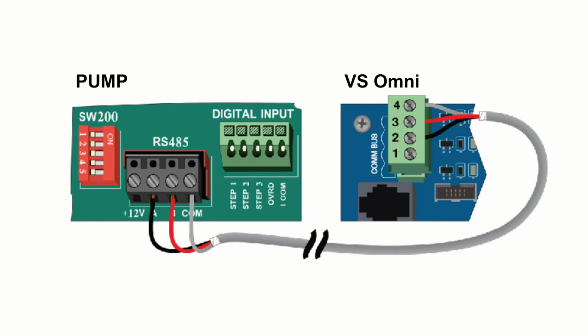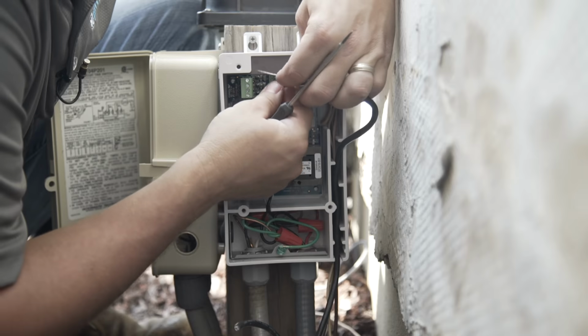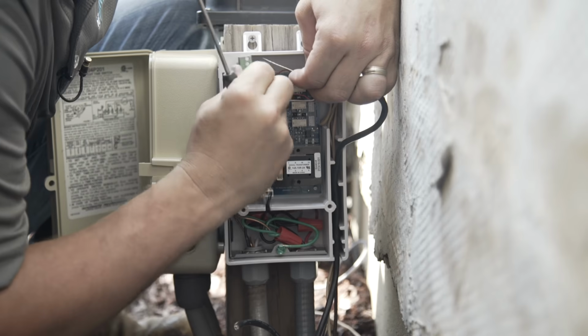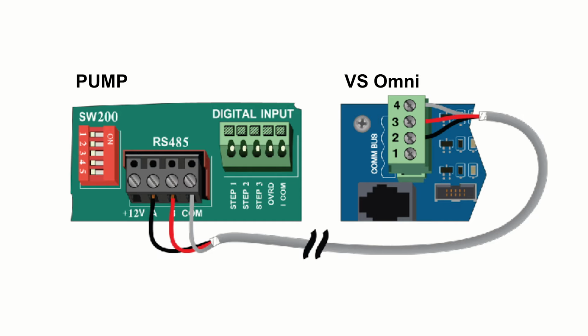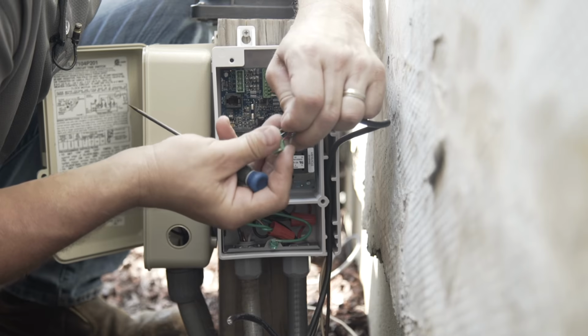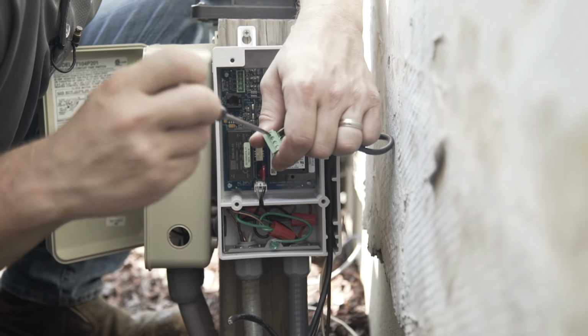Next, we need to connect the 24 AWG COM wires ran through the COM conduit between the VS pump, RS485 connector, and the wiring hub COM bus. These wires are connected as follows. A. Pump to 2 on the VS Omni wiring hub COM bus. B. Pump to 3 on the VS Omni wiring hub COM bus. COM pump to 4 on VS Omni wiring hub COM bus.